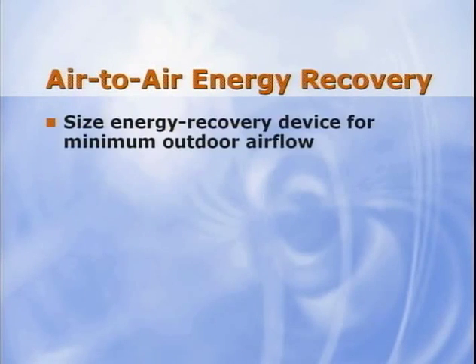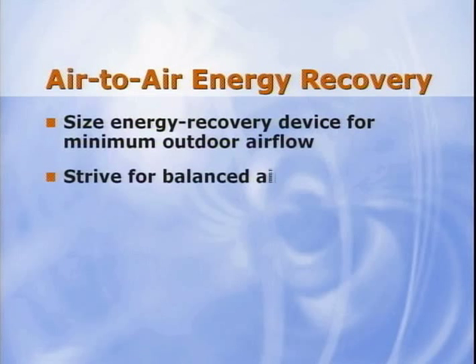First, properly size the energy recovery device. In a mixed air VAV system, size this device to precondition only the minimum outdoor airflow required for ventilation, not the maximum airflow expected during economizer operation. Bypass dampers should be used to allow for increased outdoor airflow during economizing. Second, strive for balanced airflows. Duct as much exhaust air back to the energy recovery device as possible. The less disparity between the outdoor and exhaust airflows, the more energy can be recovered.